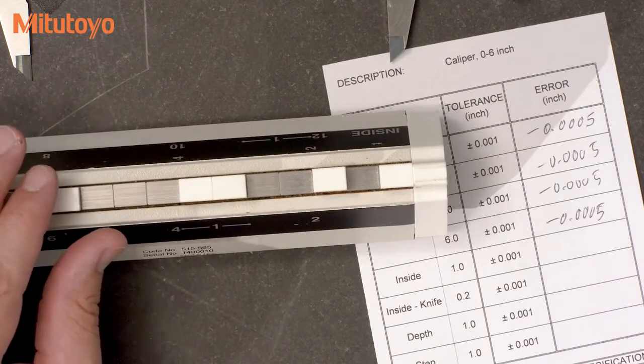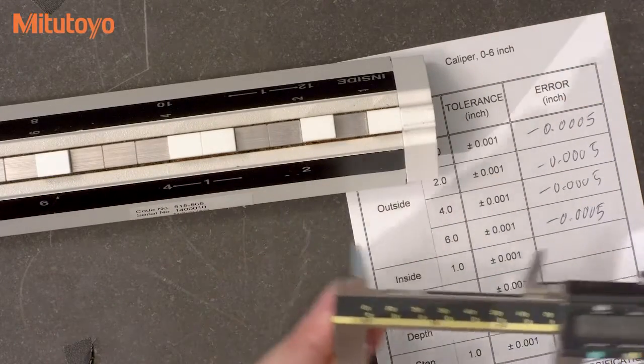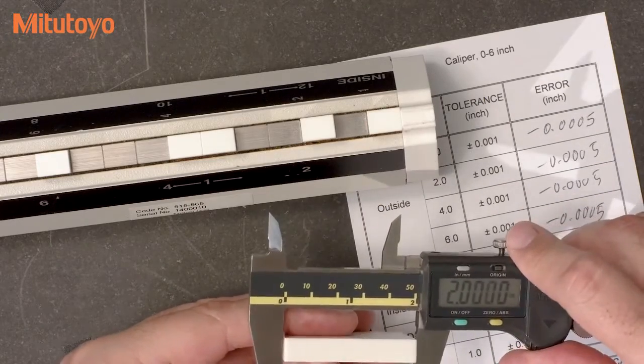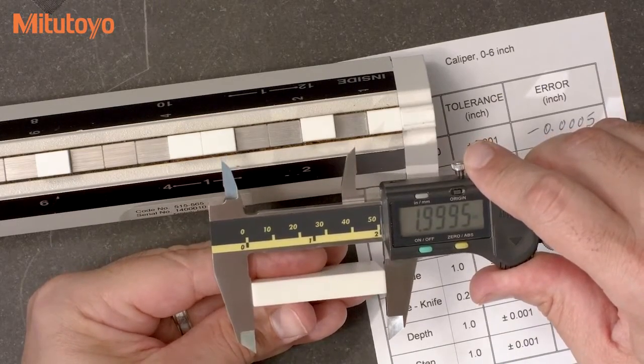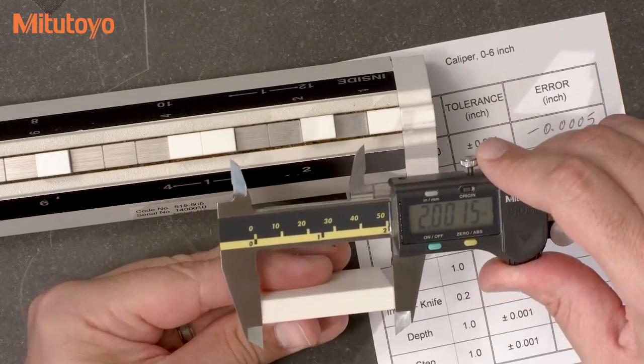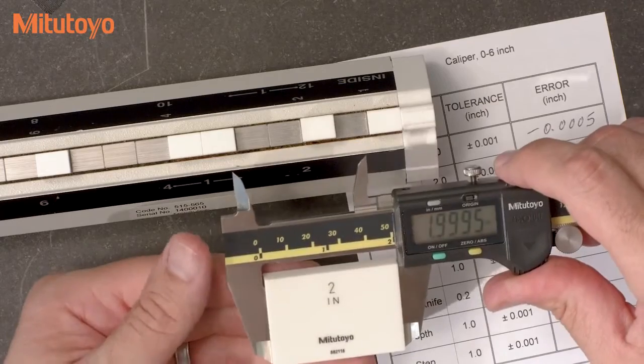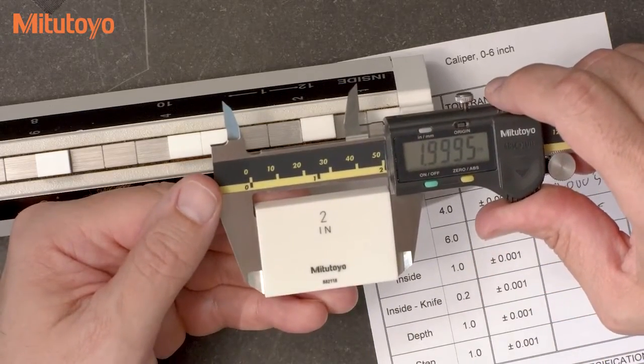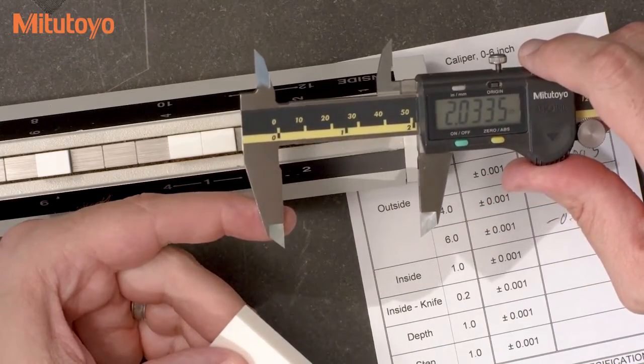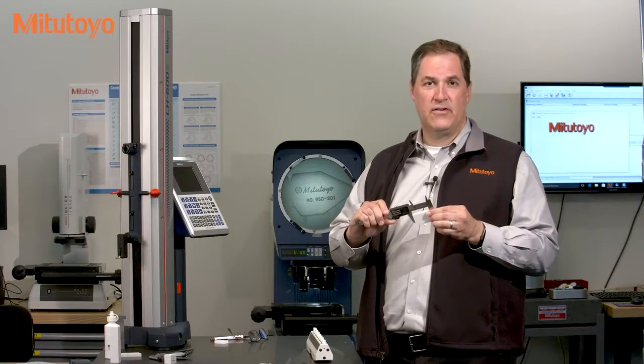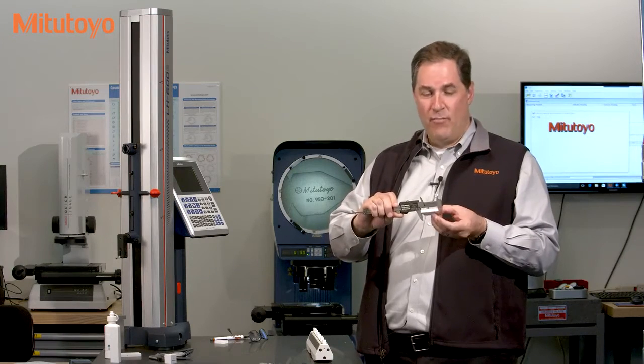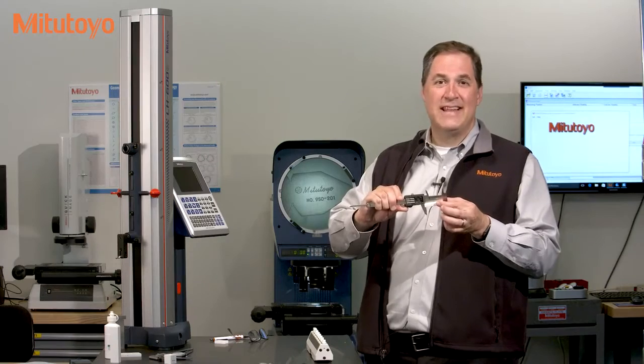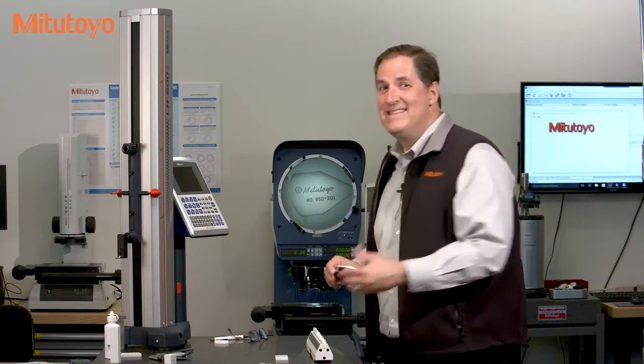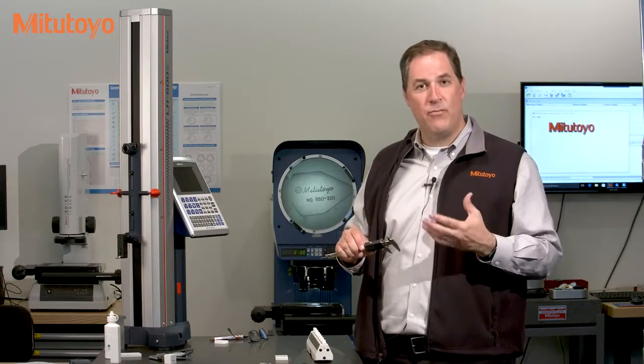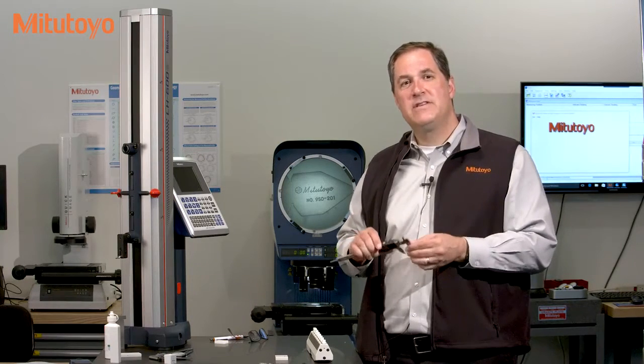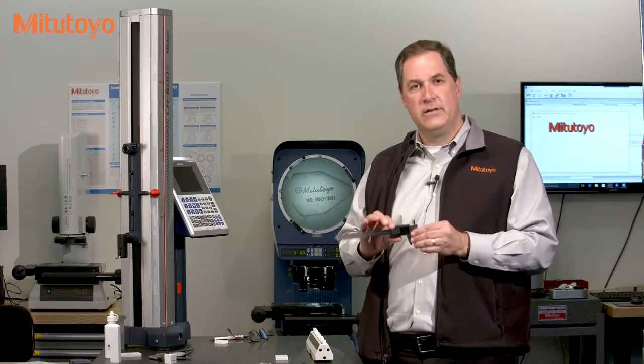An alternative to the caliper checker is to use gauge blocks. That's fine, but be careful. You need to measure them like this, because you need to move across the jaws like we showed with the caliper checker. You can't measure them like this. You want to ensure your test method is sensitive to the parallelism of the jaws. It's tempting to measure the gauge blocks across the entire measuring faces. That's easier. Or maybe to measure them only near the beam. That's usually less influenced by your force. However, it's not our job to calibrate the caliper in only its easiest or best mode of use. On the contrary, we need to assess its accuracy across any reasonable and likely use.